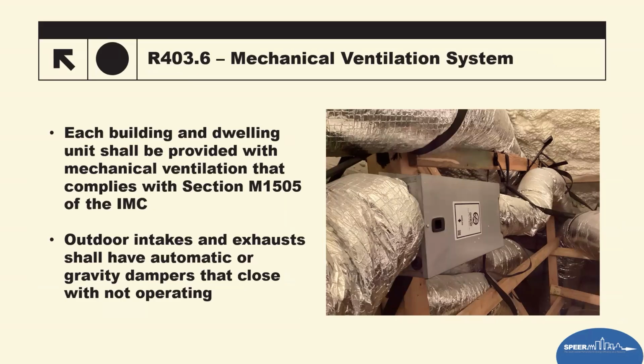So mechanical ventilation: all dwelling and sleeping units are required to have mechanical ventilation, because the highest ACH that's allowed by code now is 5. Anything 5 or less must have mechanical ventilation. Most importantly, each mechanical ventilation system must contain automatic dampers that open and close when it's not in use. The mechanical ventilation must follow section M1505 of the IMC, the International Mechanical Code. So that must also be looked at from that side of it.